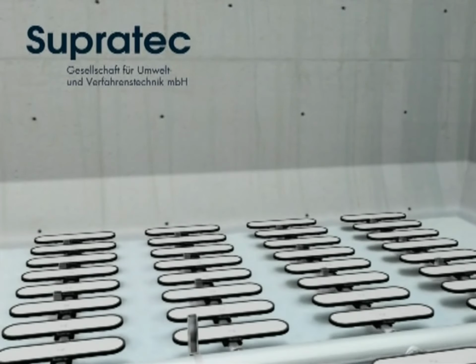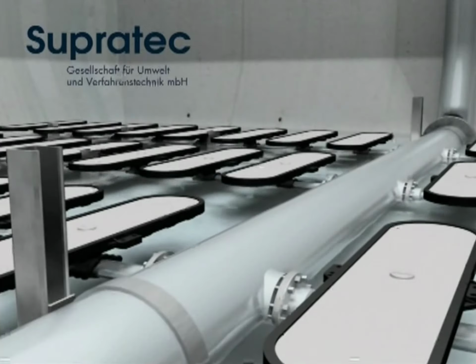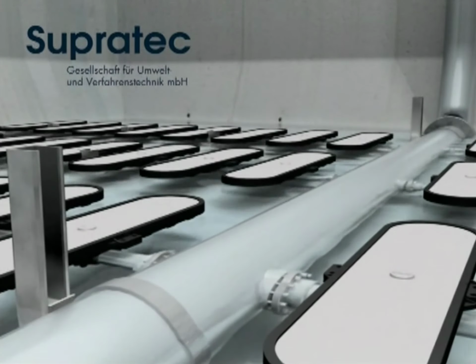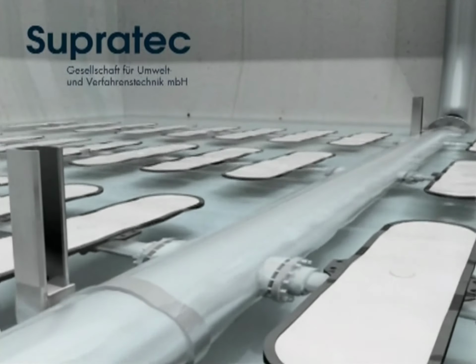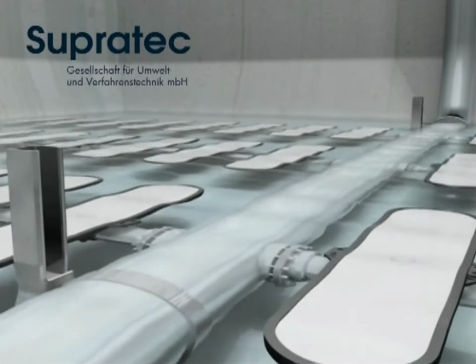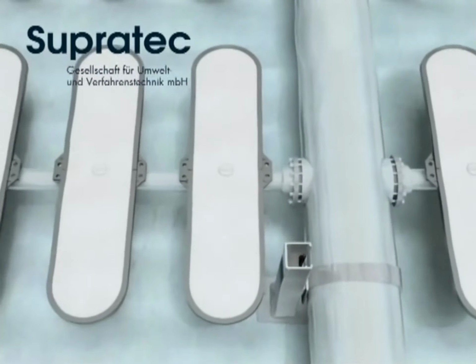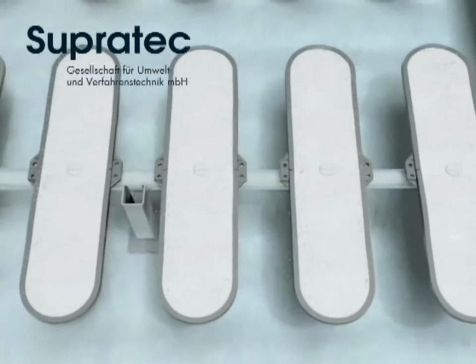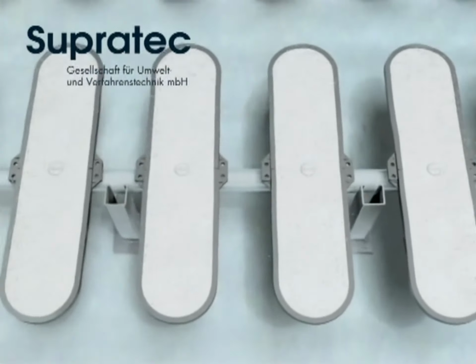A seal check should be made by trained personnel with the water level approximately 5 to 10 centimeters above the aerator. The airflow volumes to be set during inspection can be determined from the specifications in the operating manual for the respective aerator model installed.